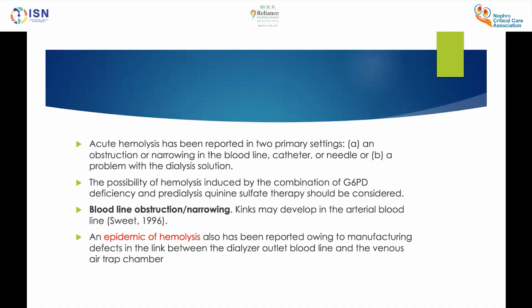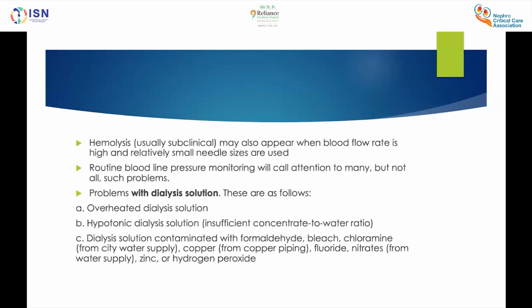And there was an epidemic of hemolysis that was reported owing to manufacturing defects in the link between the dialyzer outlet bloodline and the venous air trap chamber. Now, routine blood line pressure monitoring will call attention to many, but not all, such problems.